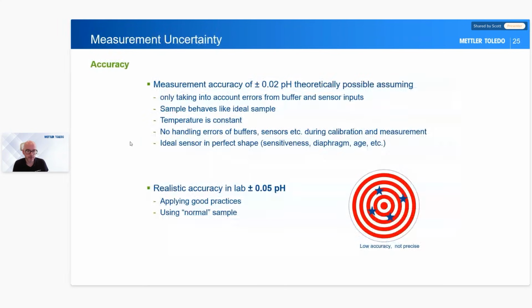So when we look here, we talk about two things. We talk about accuracy. When we're measuring the pH in a lab, what we're trying to do is take a measurement as accurate as we possibly can. Now, because of all the different parts that we've got in our system, that includes the buffers, the electrode, the wire connecting the two, the meter itself, by the time we take all those into account, what we have is what we call a measurement uncertainty, okay?